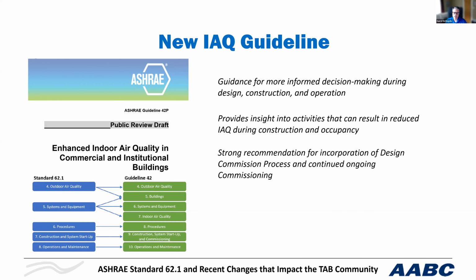It tries to clarify that commissioning starts in the design process, goes through the design review, and goes into installation, and that we do a good job in installation, that we are filtering the air, and that we're not using systems to condition the space that we're going to use in the future, or if we are, we're using good construction filters to capture all that dirt, and we're not leaving rags in the ductwork, et cetera, so that TAB can't do their job. And of course, with respect to TAB, it's important to say it's a living document. Things happen, the occupancy changes, design assumptions may not have been correct to begin with. It should be evergreen, it should always be changing.